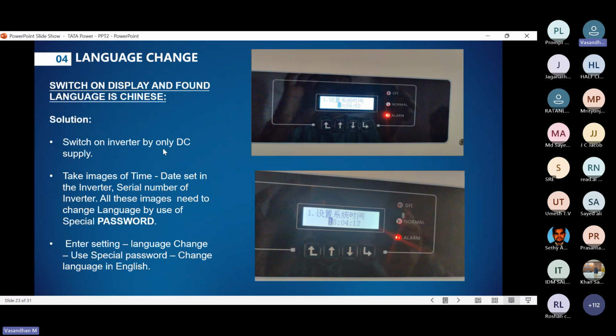Switch on the DC DB only or the DC switch and take a photo of the screen showing the series, like year, month, date and time below it, for example 18/4, hour, minute and seconds. We take this photo for reference, along with the serial number. Then go to settings, where the language change option is available. Use the special password 0001 and change the language to English. That's it, simple steps, and this is also available in the user manual.